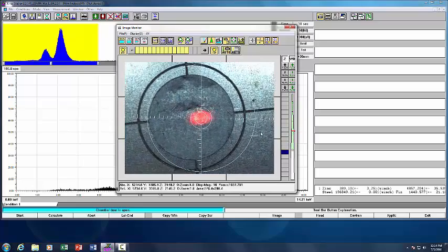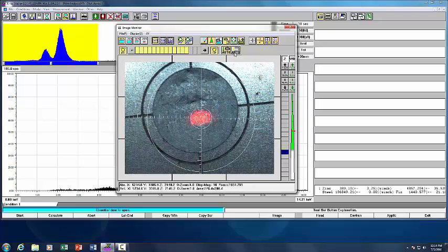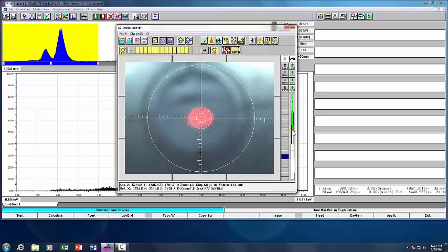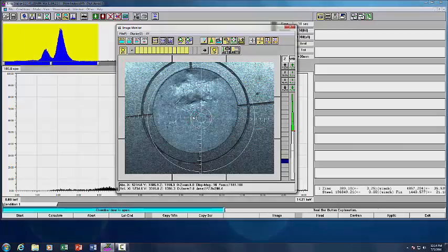Automatically moves the camera, but our head did not move. It indicates the head movement over here in the green arrows. We want it to be at the red mark here. That's that focal depth that we calibrated at. Let's hit auto approach. It moves the head to the distance we calibrated at. Readjust the camera.